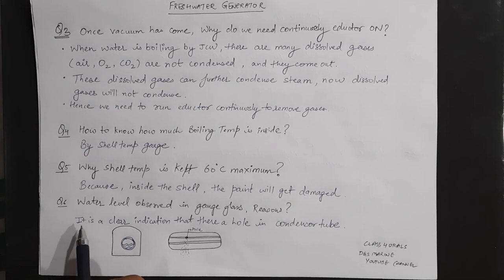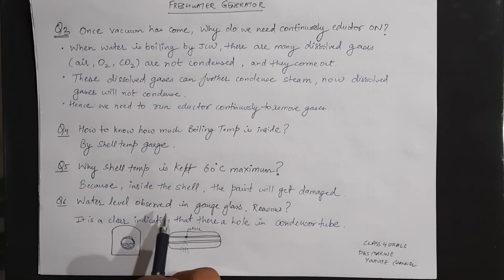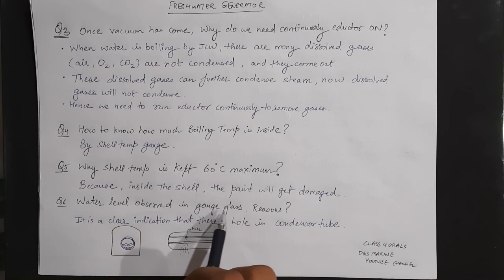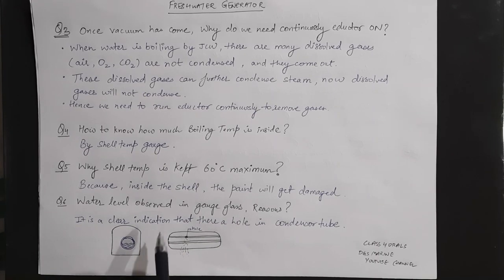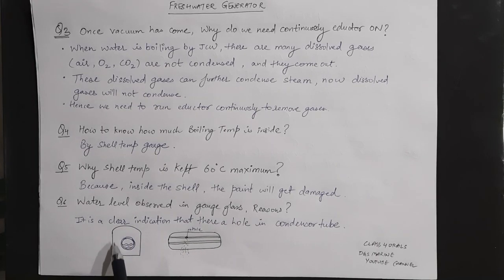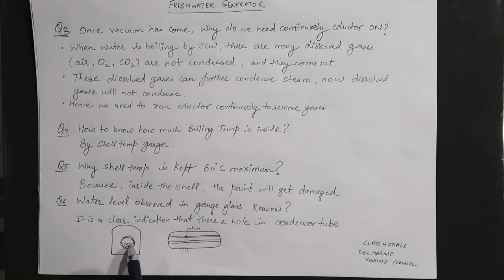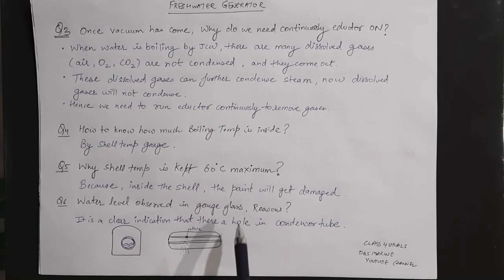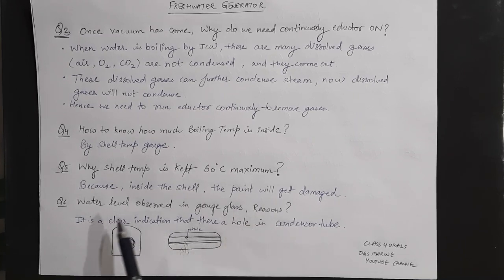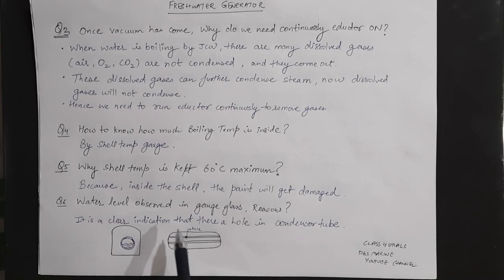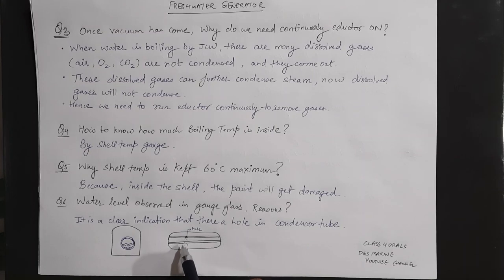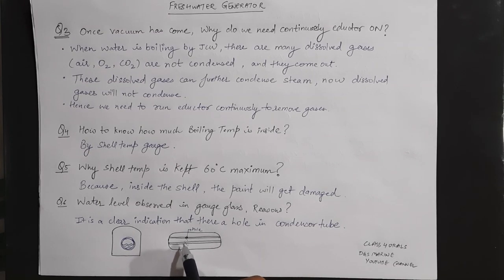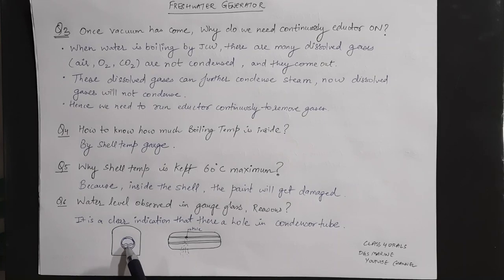Question number 6: water level is observed in the gauge glass of the fresh water generator. Suppose water is being observed here in the gauge glass. What is the reason for this? It is a clear indication that there is a hole in the condenser tube, and water is being leaked from this hole, filling the level area of the gauge glass.